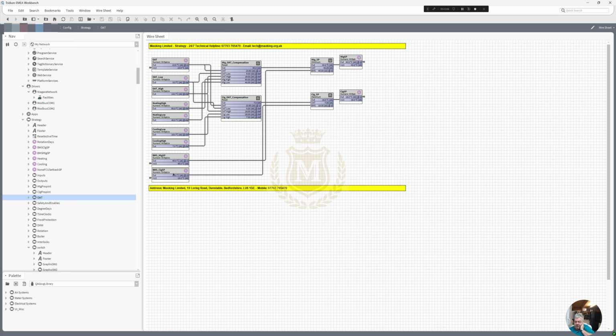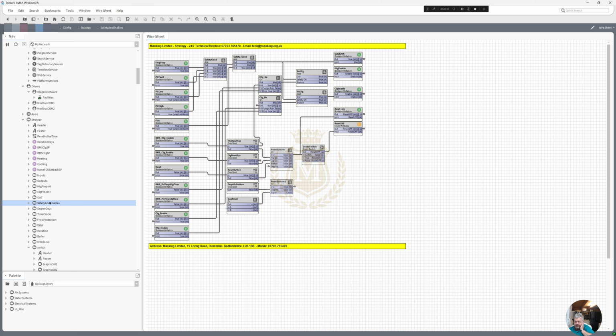I think the client is just using fixed, and I don't think they are using this. In fact, they are BMS 40, BMS 16, the maximum, yes, and the minimum. So they are using the fixed, not the outside air compensation, i.e. 40 and 16 are our two temperatures. Safety and enables folder, so pressurization and your emergency stops. Simple enough. Safety okay, heating enable, cooling enable. We're not doing any heating though because of the outside air temperature.